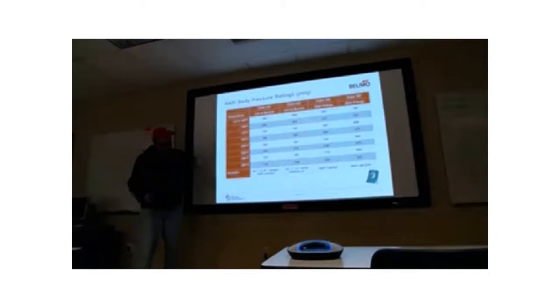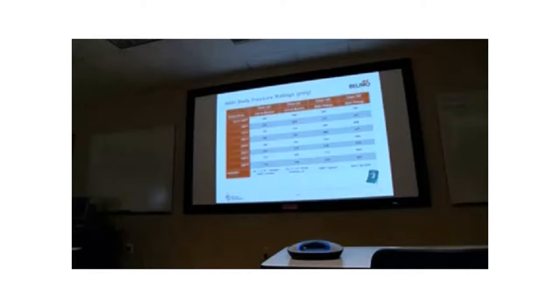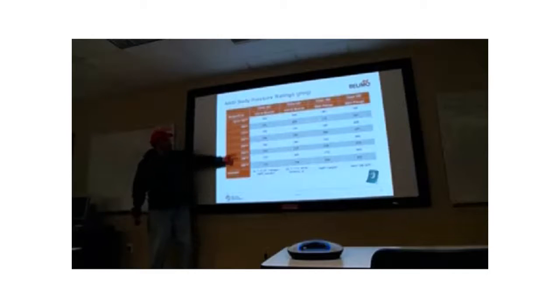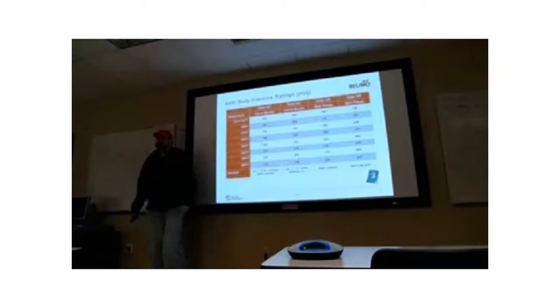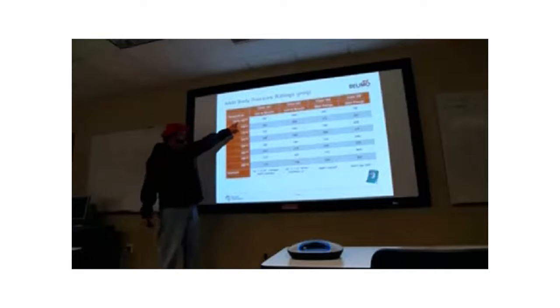But here's what I want to get across. When you have body ratings for the different classes, people think, okay, it's ANSI 125, I can only have 125 psi on that valve, or it's going to leak, or it's not going to hold, right? It's not true. It's a function of temperature. So if you look here, let's just take class 125. This would be like a globe valve or an iron or bronze cast valve. If you have chilled water, so if your water is less than 100 degrees, you can go up to 200 psi. It's not 125, it's 200 psi. If you go all the way out to class 300 with chilled water, you can have 740 psi before you're going to have some issues.